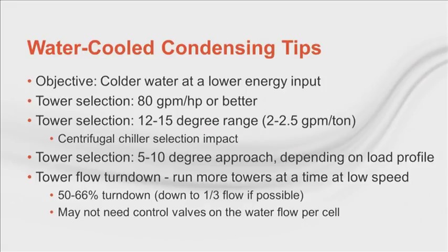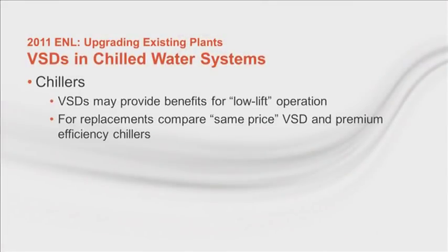Flow turndown is accomplished with special nozzles, cups, or dams inside the tower to keep the tower fill uniformly wet. Now here are some takeaways from our 2011 Engineers Newsletter Live on upgrading existing chilled water plants. As Mike mentioned in the beginning of this program, variable speed drives are becoming commonplace on centrifugal chillers. But what about adding one to an existing centrifugal chiller?